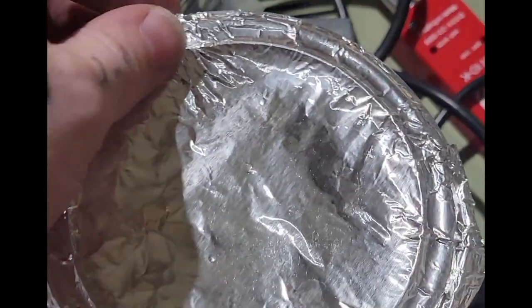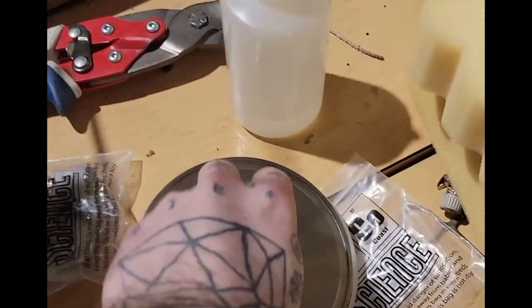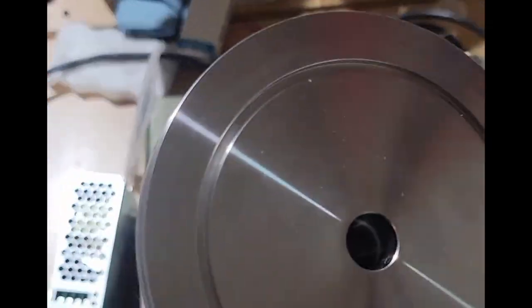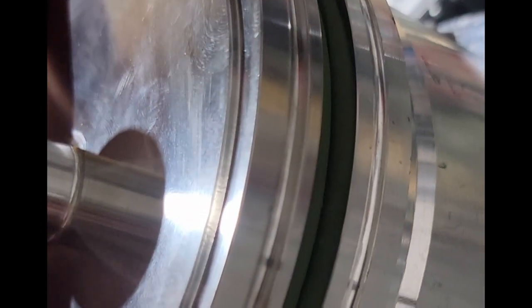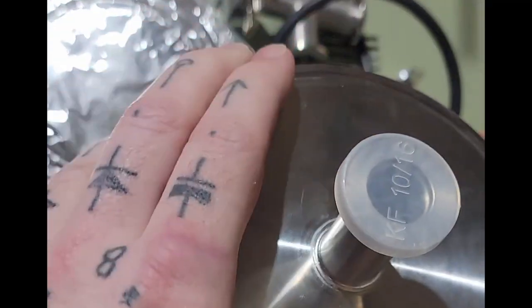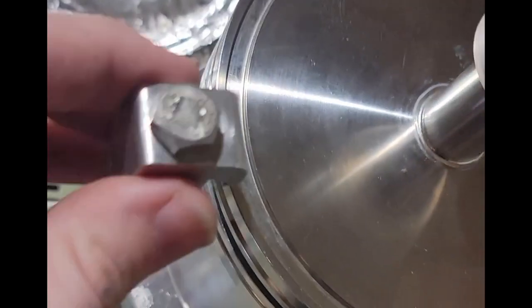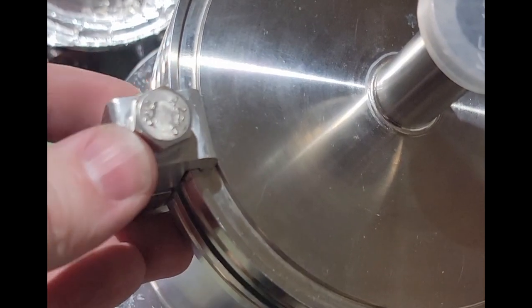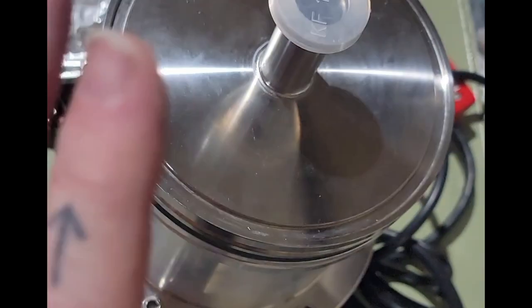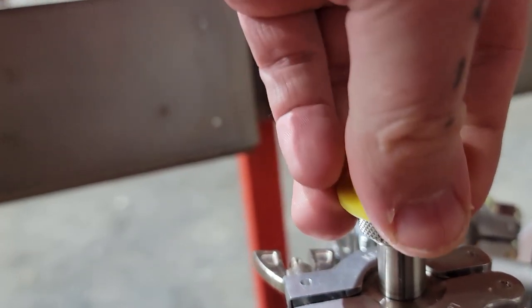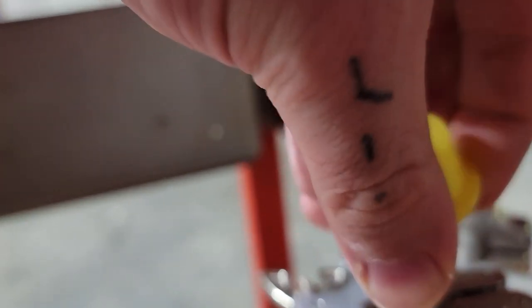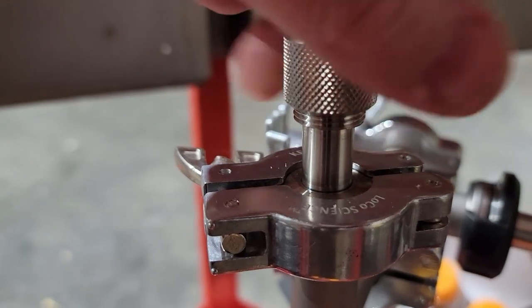Finally, there's the ISO large flange standard, which is also known as the LF, MF, or usually just ISO flange. These work on the same principle as the KF flange, but they can be much larger. ISO flanges basically come in two flavors. The ISO K flange, which is connected with clamps, kind of like a KF flange, and the ISO F flange, which is connected with bolts, in the style of the Conflat. With the proper single-sided clamps, you can even connect ISO K to ISO F flanges.